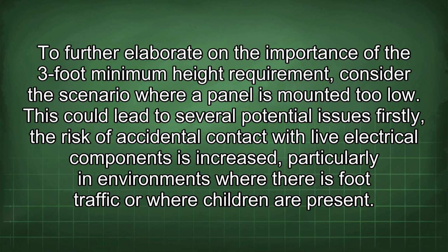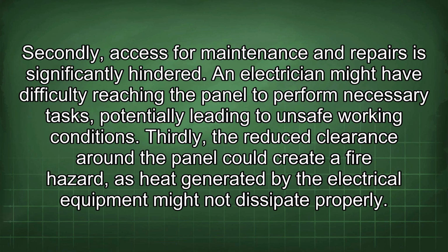To further elaborate on the importance of the 3-foot minimum height requirement, consider the scenario where a panel is mounted too low. This could lead to several potential issues. Firstly, the risk of accidental contact with live electrical components is increased, particularly in environments where there is foot traffic or where children are present. Secondly, access for maintenance and repairs is significantly hindered. An electrician might have difficulty reaching the panel to perform necessary tasks, potentially leading to unsafe working conditions.